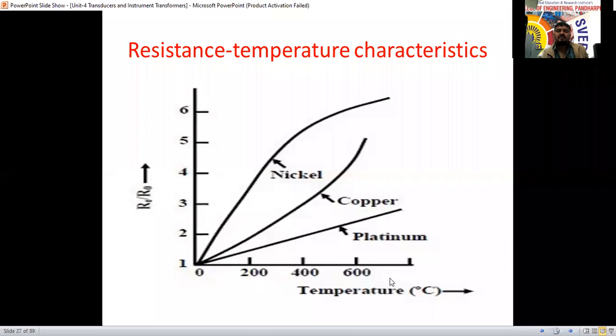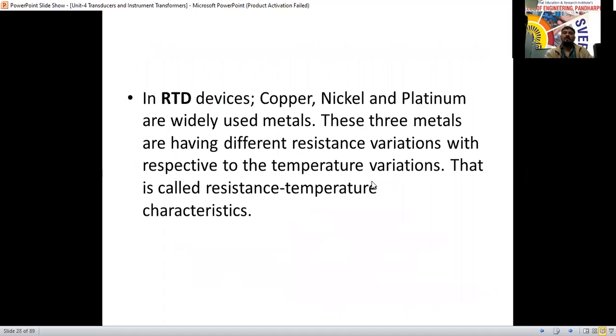So the characteristic is different based on the material. The resistance is linearly proportional to the temperature for the copper material. For nickel, it is the square of the resistance. For platinum, there is a very slow or small change in the resistance. This is the temperature and resistance characteristics. So it completes the construction, working, and its characteristics. Now the RTD has some advantages here.